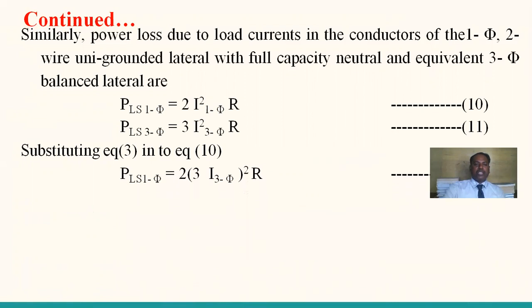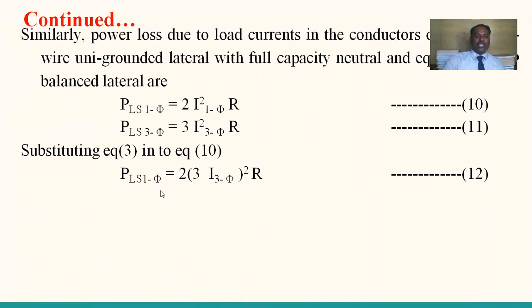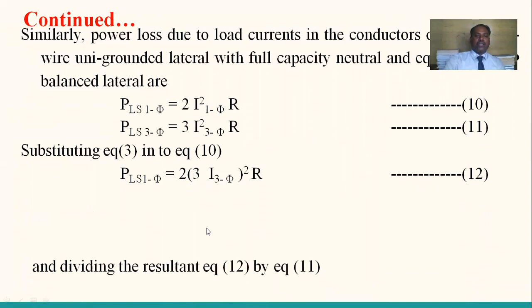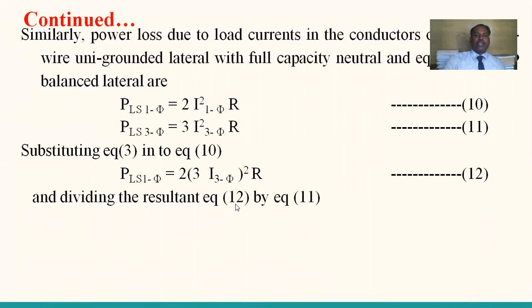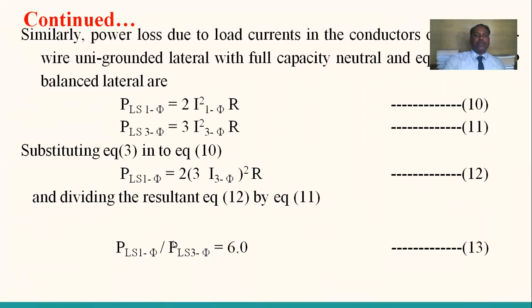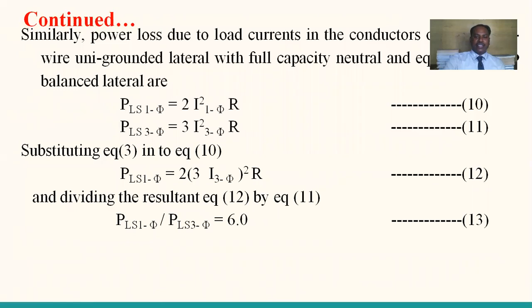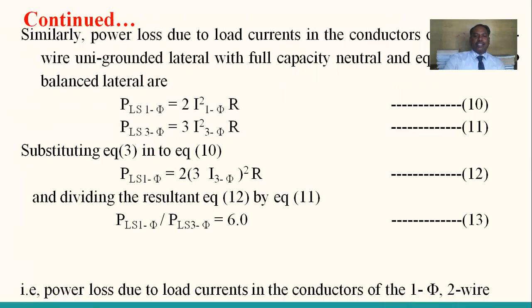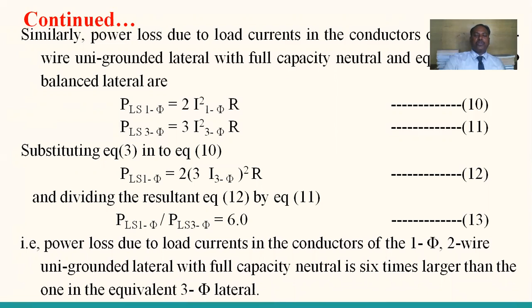So you can substitute this. The power loss of a single phase system is equal to 2 times 3 into I3 phase whole square into R. And dividing the resultant equation 12 by equation 11, that is PLS of single phase by PLS of 3 phase is equal to 6. Therefore, power losses due to load currents in the conductors of the single phase 2-wire uni-grounded lateral with full capacity neutral is 6 times larger than the one in the equivalent 3-phase lateral.